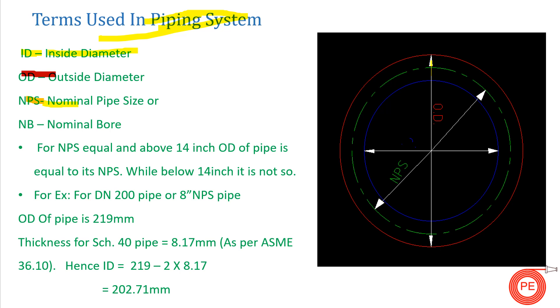With the help of nominal pipe size or nominal bore, we designate pipes in the market. When we buy a pipe, we don't say we need a pipe of OD 219 mm; instead, we say we need a pipe of DN 200, or in the NPS inch system, we say we require an 8-inch pipe. For large pipe sizes above 14 inch, the NPS lies between OD and ID, but for small pipes like 1 inch, 1.5 inch, or 2 inch, NPS can even fall outside that range.